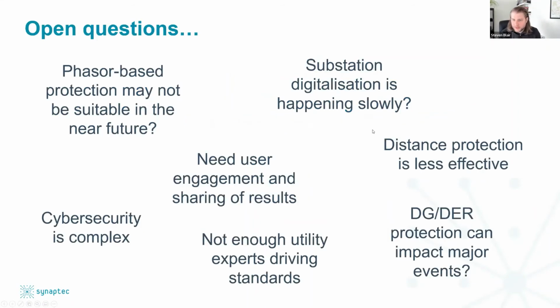Again, this is intended to be provocative, and what we're providing here is a bunch of statements about how we see protection at the moment, how we see it evolving in the near future, and what issues we're observing. So to quickly sum these up: phasor-based protection has been the norm for a long time, but perhaps with a massive proportion of converter-interfaced generation, and maybe even a purely converter-based grid, the waveforms you might see during a fault could be quite radically different to what we're used to for a standard fault response. So maybe a phasor-based approach isn't suitable anymore. I'm not sure about that, to be honest, but there's probably some research to be done there.